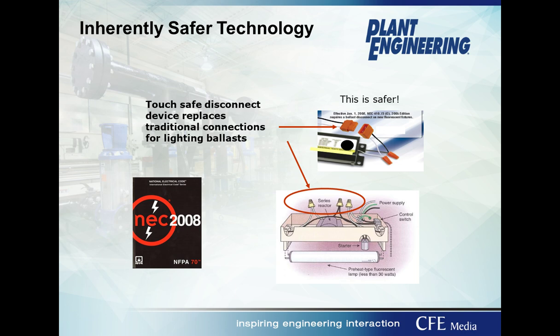This is an example of inherently safer technology that was required in the 2008 National Electrical Code. This had to do with reducing the risk of disconnecting ballasts in fluorescent light fixtures or other luminaires that had ballast-type devices that may need replacement from time to time. The requirement, shown in the upper right-hand corner of this photograph, is the touch-safe disconnect device that allows an electrician to disconnect the ballast without having to turn off the power to the circuit.